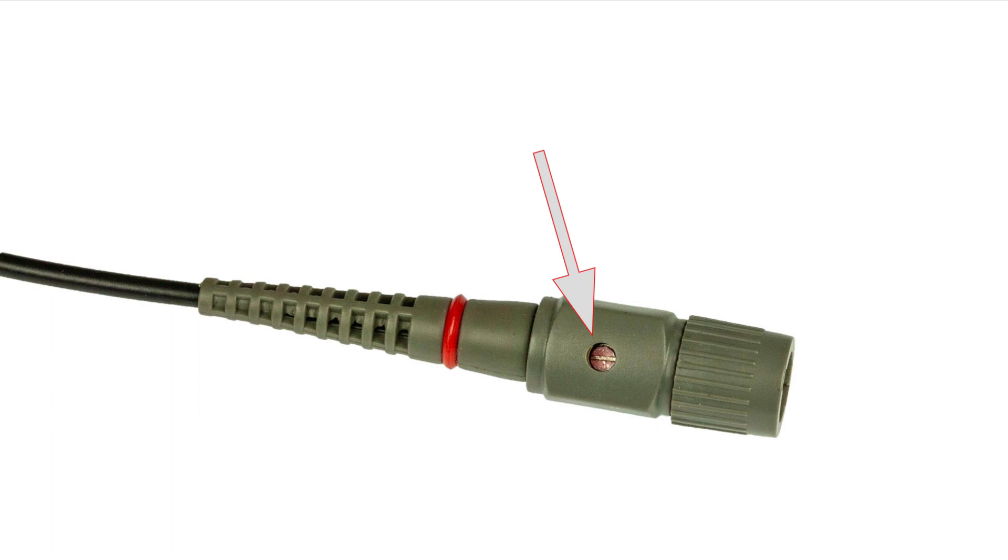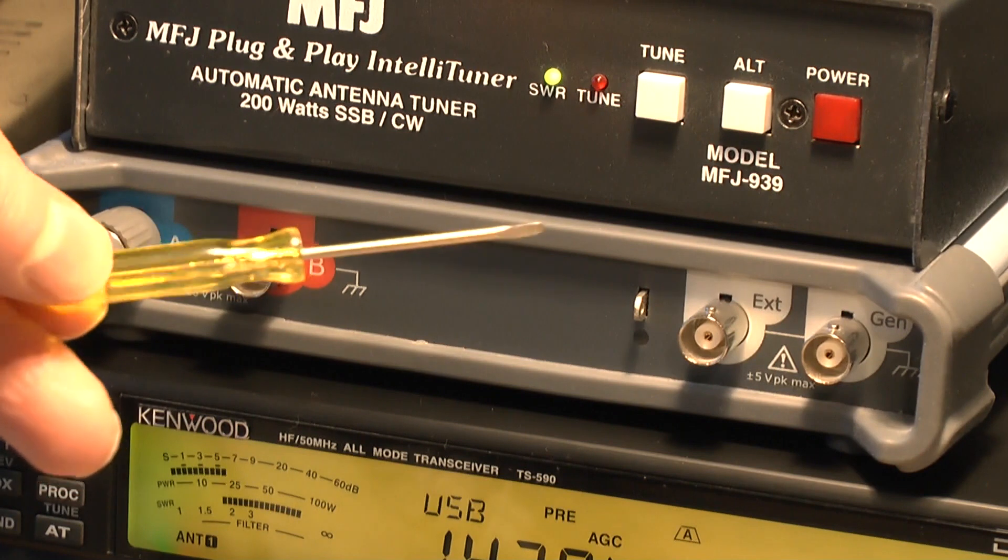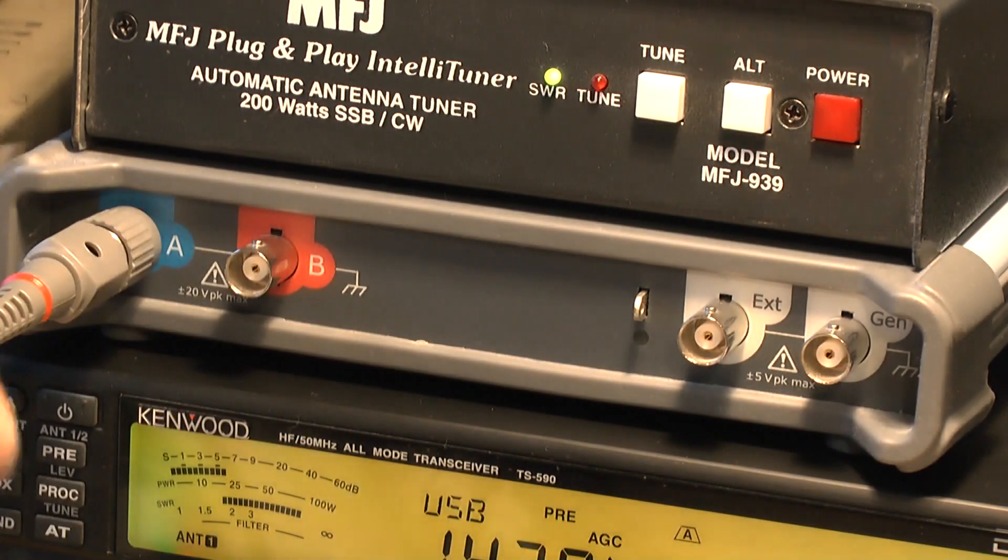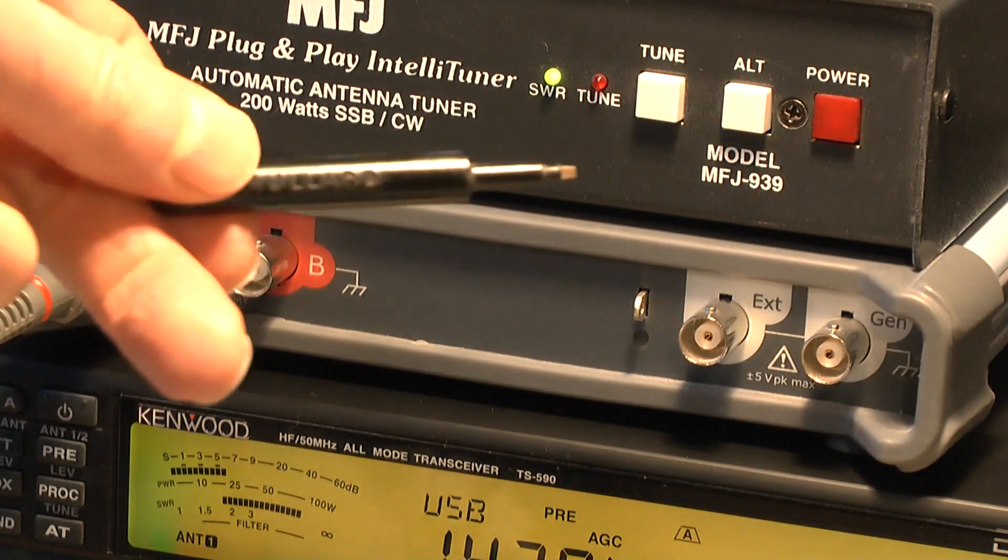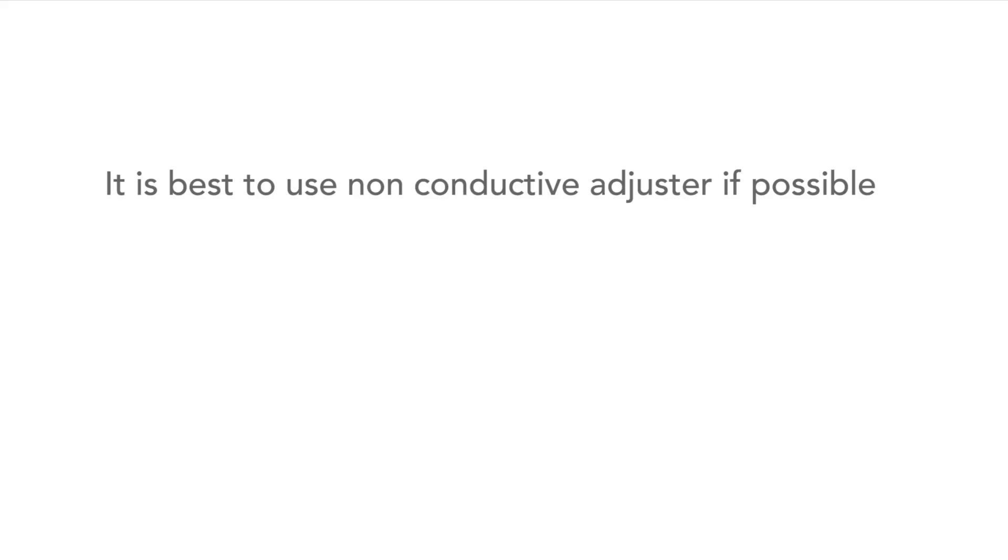A small adjuster with a screwdriver slot will be seen in a hole on the probe. Often people will use a small metal screwdriver for the adjustment, but ideally a non-conductive tool should be used because it's less likely to affect any readings as a result of any stray capacitances. It's not essential but a very good idea.